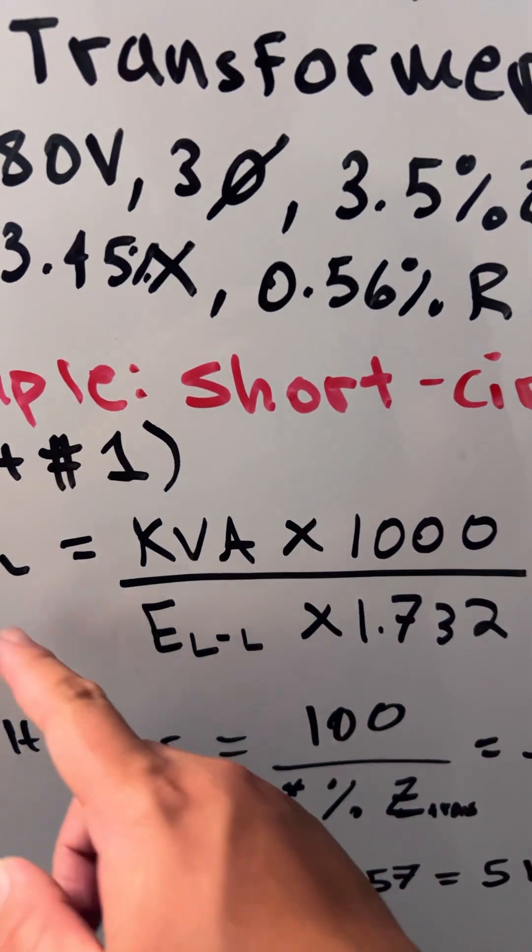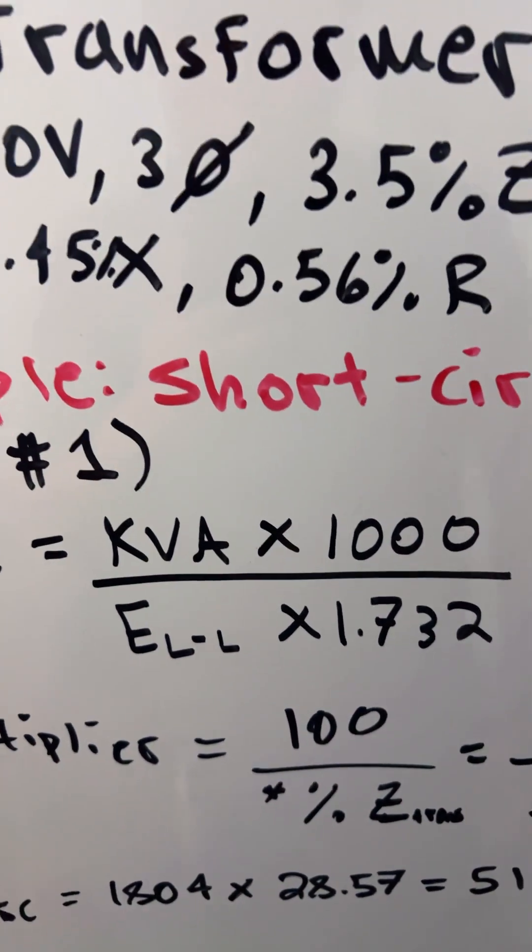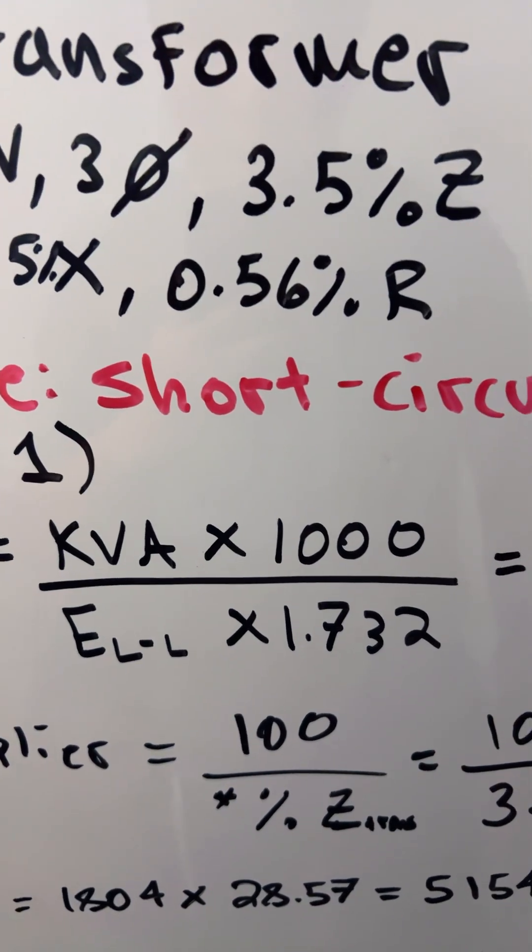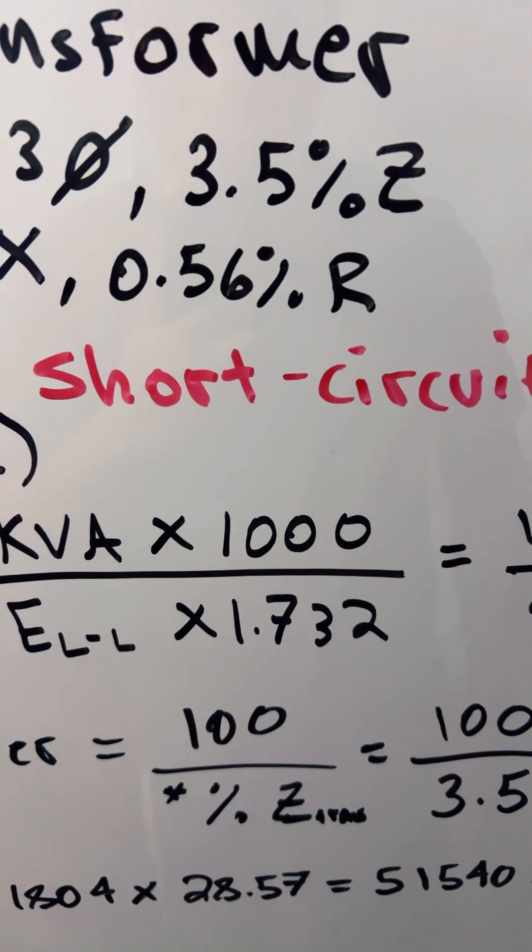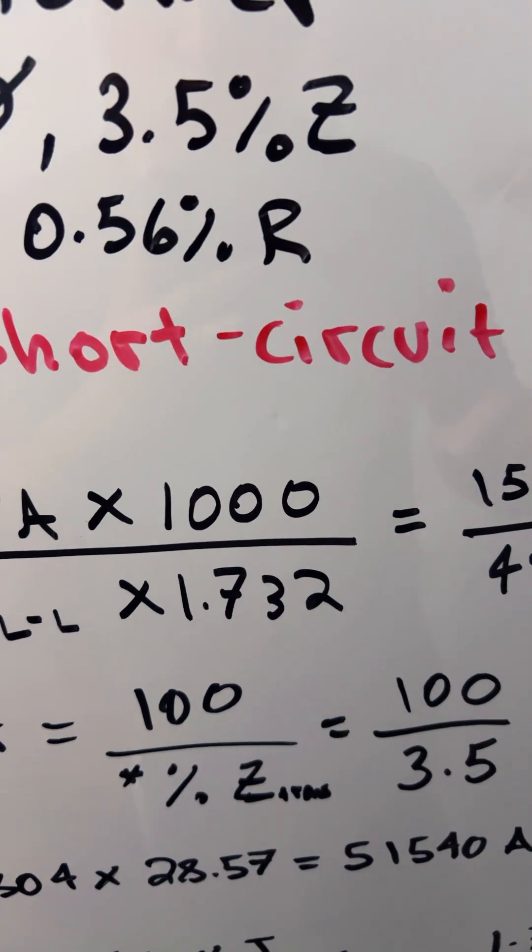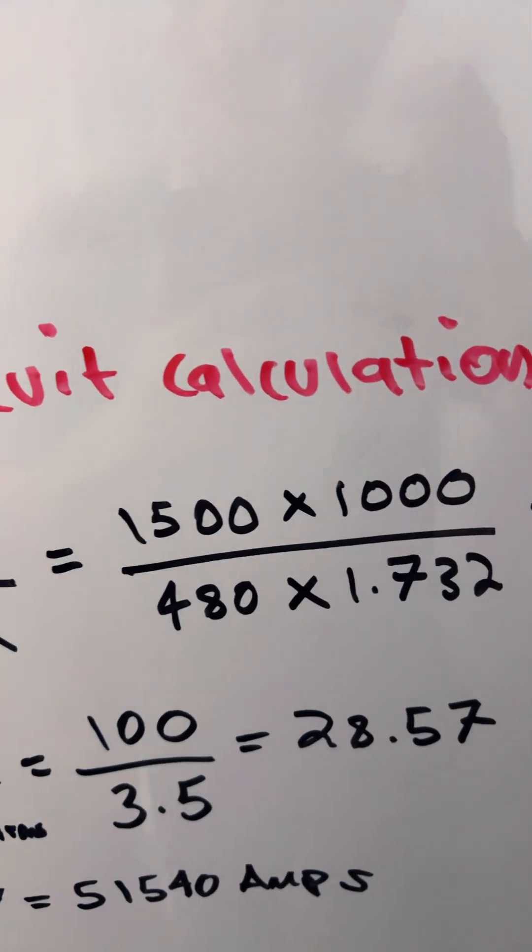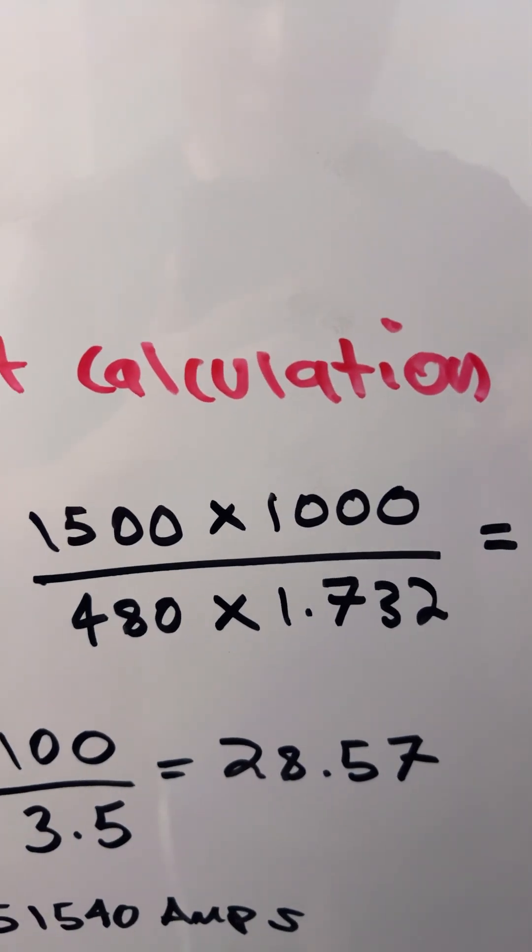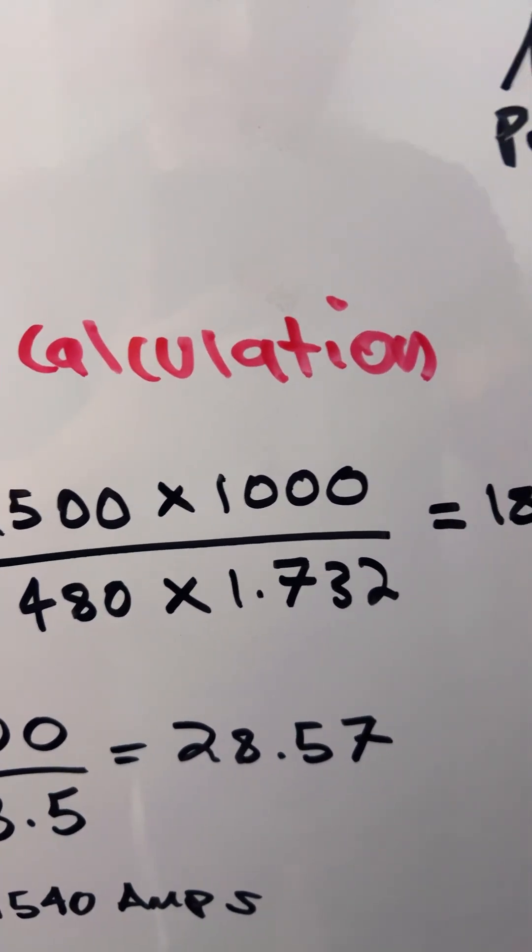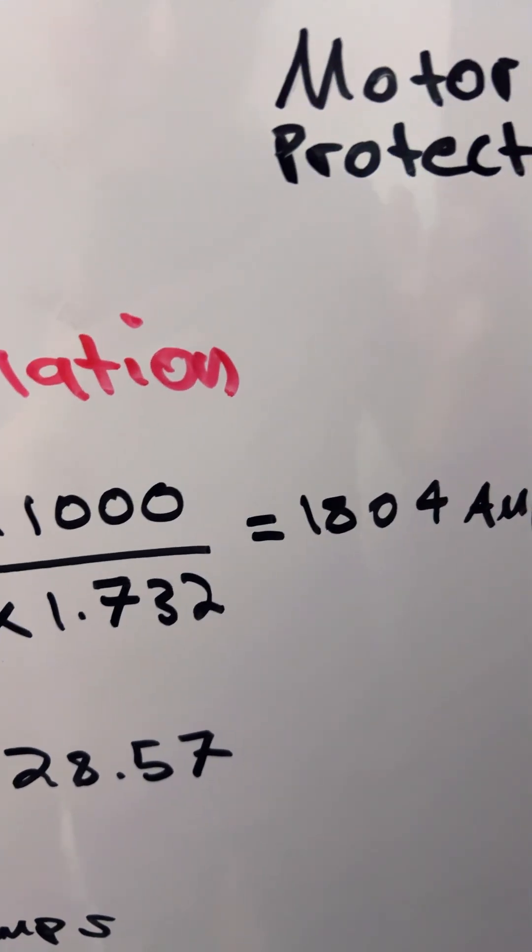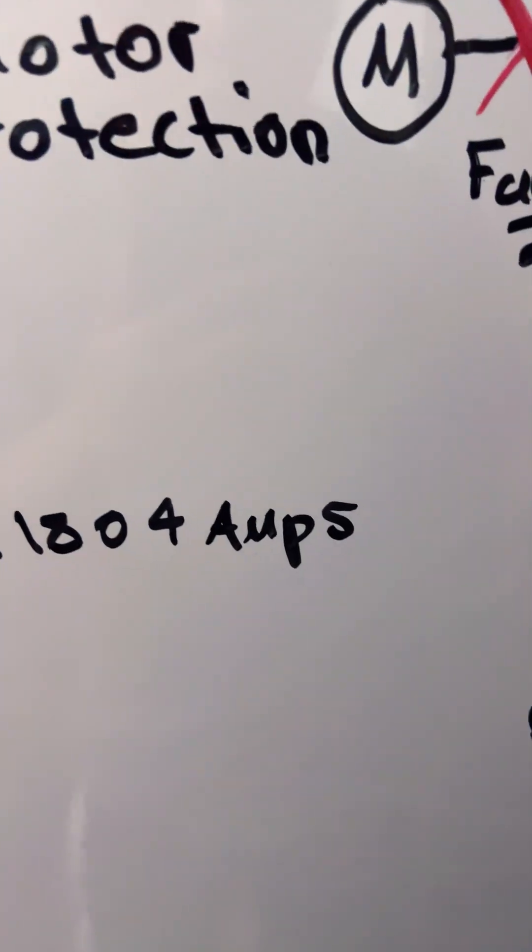Line-to-line amps equals kVA times 1000 divided by line-to-line voltage times 1.732, which is square root of 3. This equals 1500 times 1000 divided by 480 volts times square root of 3, which equals 1804 amps.